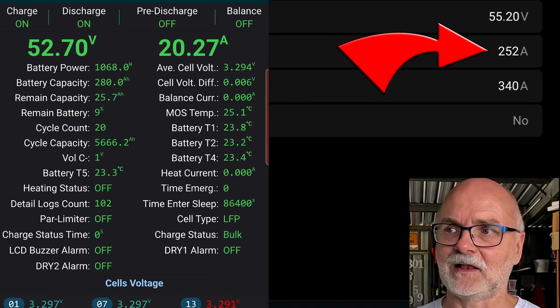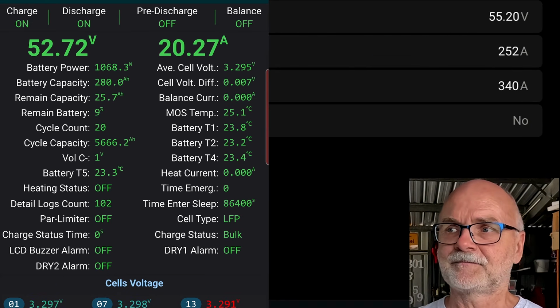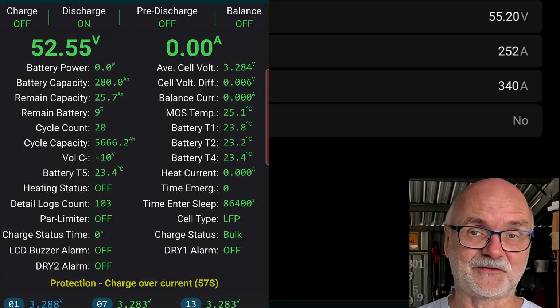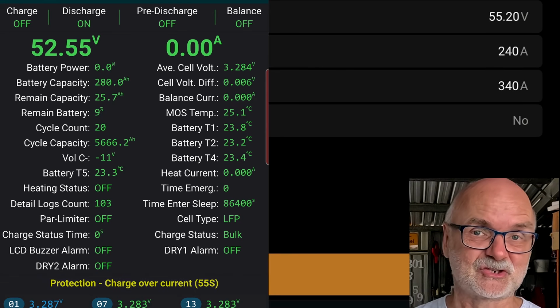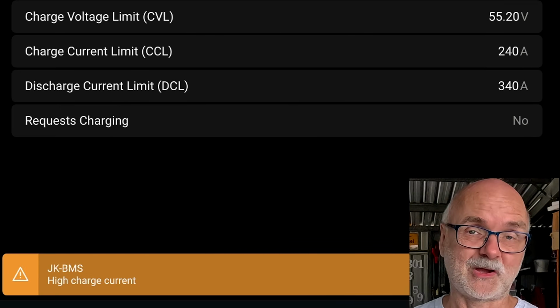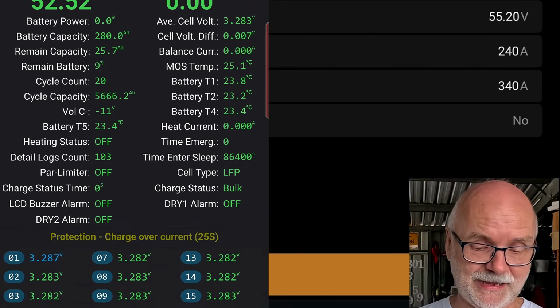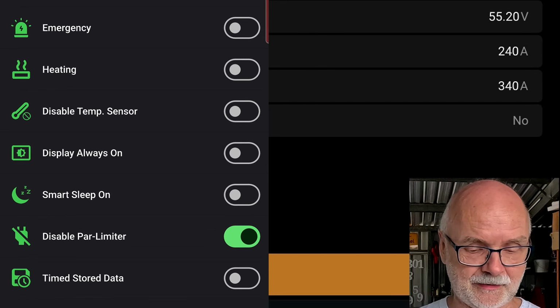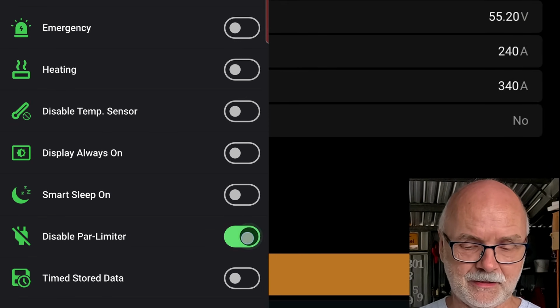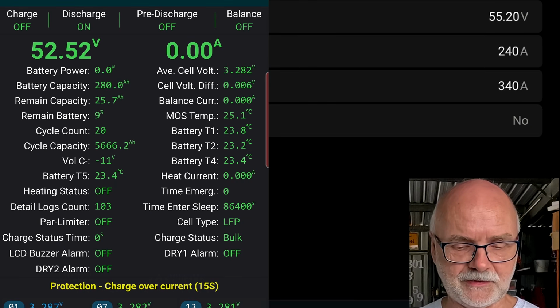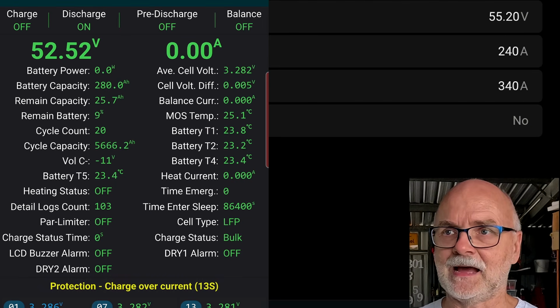We can see the CCL goes up again. Everything is good. Now the next alarm comes because after 3 seconds it realizes the charge current is still too high. So we're going back into alarm. Okay, so now let me turn on this parallel limiter. Yeah. Bam. So let's give it another 15 seconds until the alarm clears.